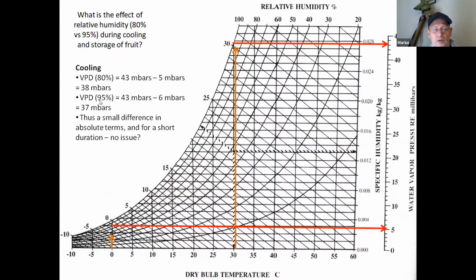If I have a cold room running at 95% humidity, which is the recommendation, the fruit is still going to be running up at 43 millibars, but now the cold room is at a higher humidity of 95%, which is halfway between the 90 and the 100. So that's the one right over there. If we look at the vapor pressure on the right, we see that at 6 millibars, that gives me a deficit of 37. So the bad cold room has a vapor pressure deficit of 38. The good cold room is only 37. So there's, in absolute terms, a very small difference between the two.